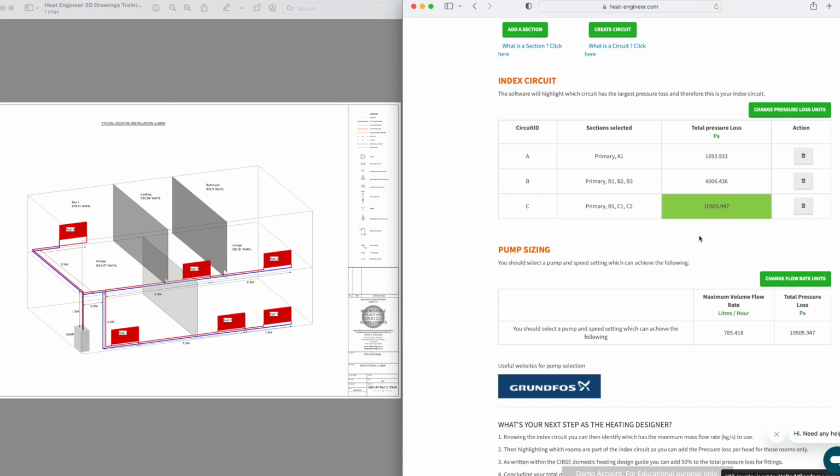Now, if you imagine that bit of 15 mil pipe that's teed into the middle of that 28 mil pipework, and then 2 inches either side of that 15 millimeter pipework, there's another T piece with the same amount of 15mm pipe sticking in it, but it only comes up, say, I don't know, 950 millimeters. It drops 50 millimeters each time, but you keep adding T's all the way down, so you create this kind of pyramid shape of pipework going down either side, right the way to the end. As I say, it doesn't matter if it's a metre long or a mile long, it makes no difference.